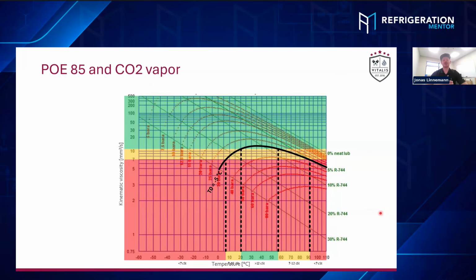Let's say that way, you can't really change the suction saturation temperature, right? You need it to maintain your cooling capacity. So you're more or less stuck with that. But you can take care of having the right oil temperature inside the compressor to be in that green spot or maybe in the orange spot, right? Okay. So it's all coming back to the oil temperature itself. Yep. And the oil pressure or the CO2 pressure with the oil is important for oil storage and oil separation, but in the compressor you can't change it, right? That makes sense.